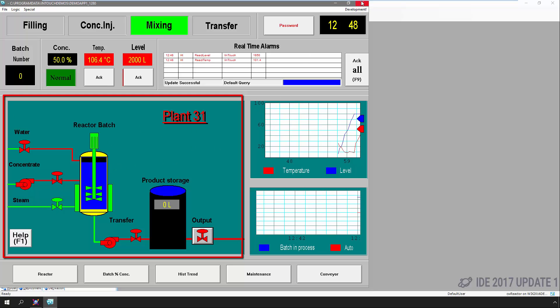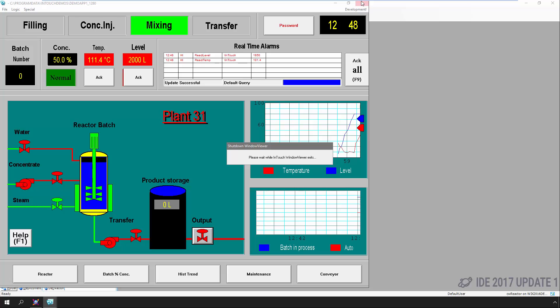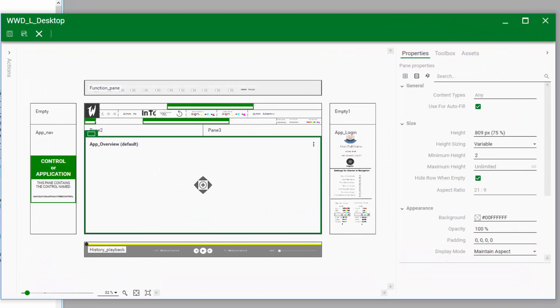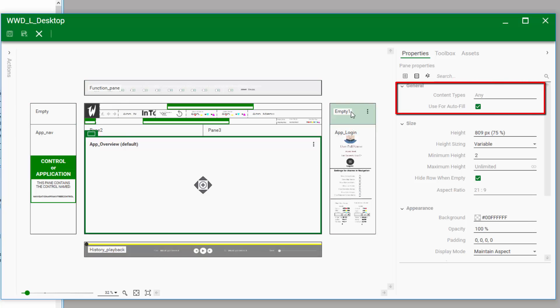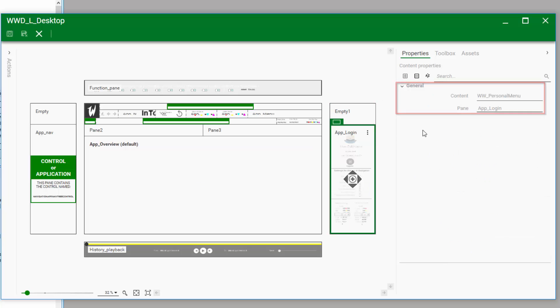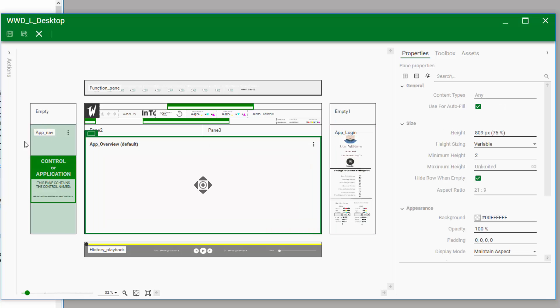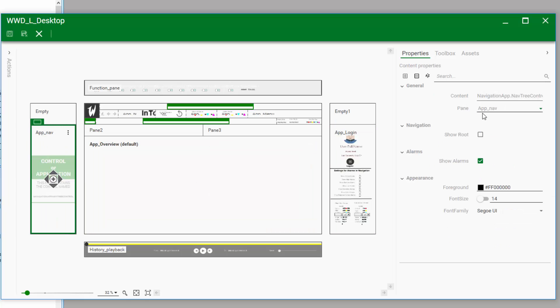They might also have a dedicated area for alarm summaries or historization, and there's always a dedicated area where the main content is shown. InTouch OMI utilizes layouts in a similar way, but it automates what content is actually shown. In other words, you don't actually create any windows inside InTouch OMI. You simply create panels within a layout and tell the layout what type of content should be visualized in each panel.